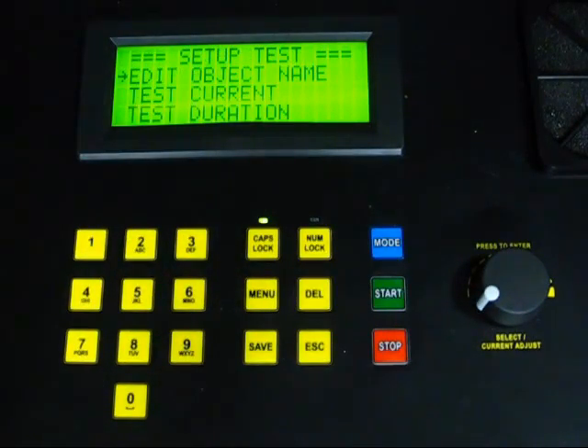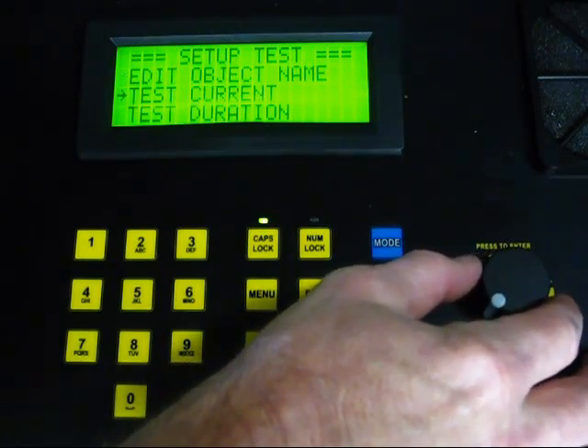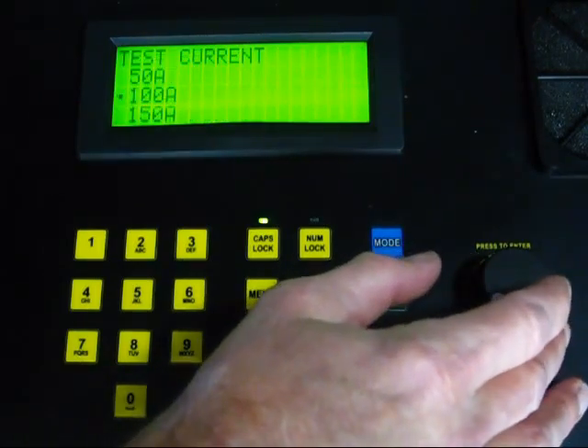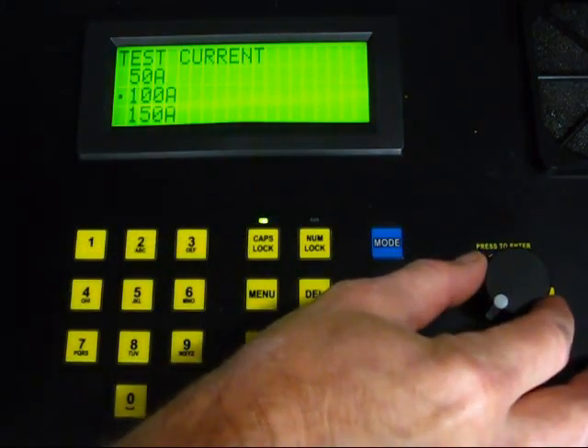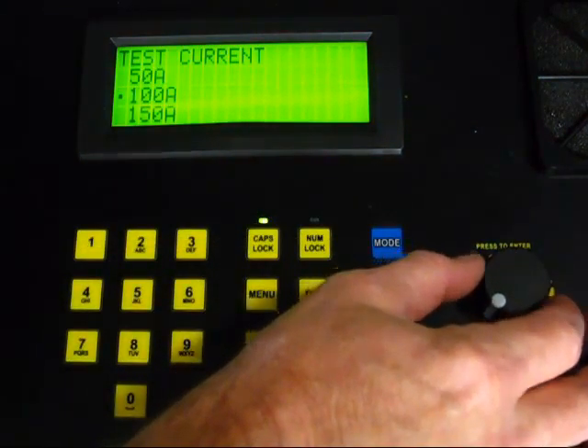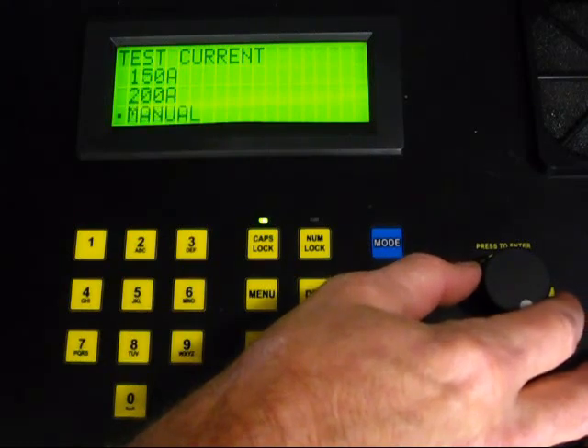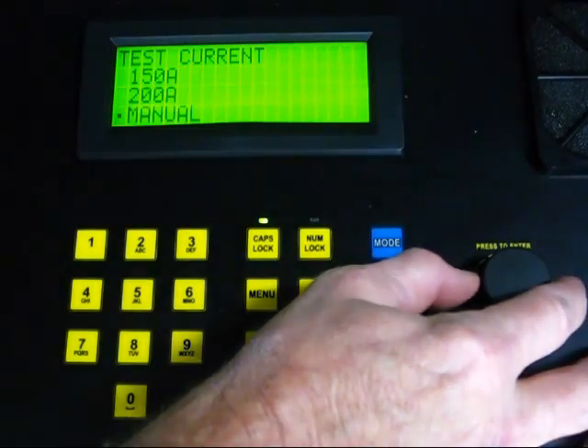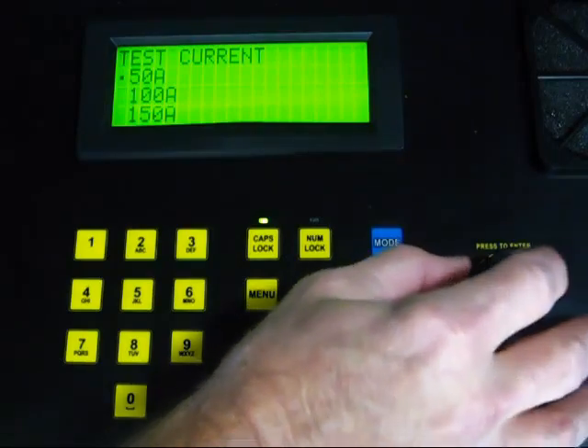Then, turn the rotary knob counterclockwise to move the selection arrow on the LCD screen down to the option Test Current. Press the rotary knob to display the Test Current menu. Turn the knob to select the current setting for the test. The menu offers four fixed current settings: 50, 100, 150, and 200 amps. You can also select the Manual option. This option allows you to control the amperage during the test by turning the rotary knob. In Manual mode, the current is limited to 100 amps. In our test, we will choose 50 amps.